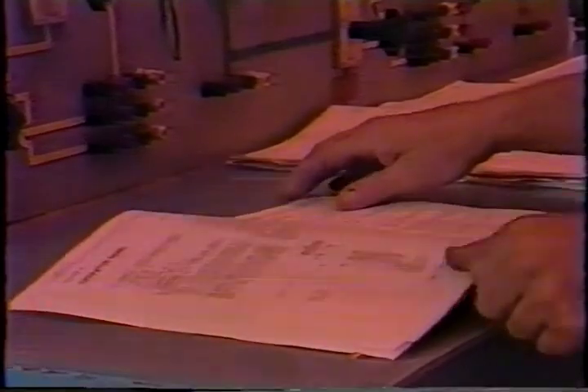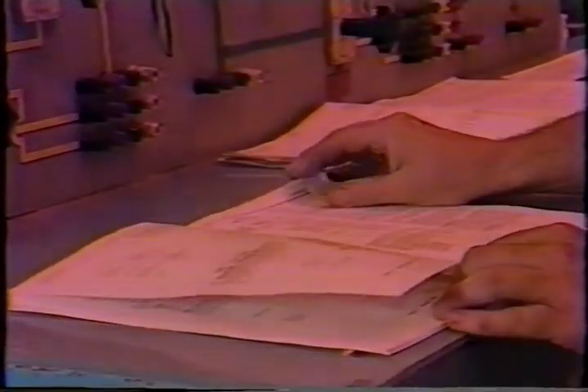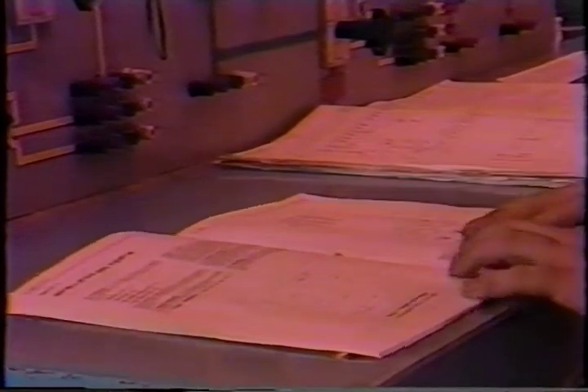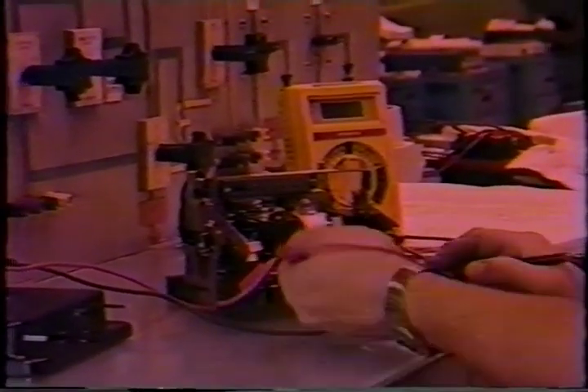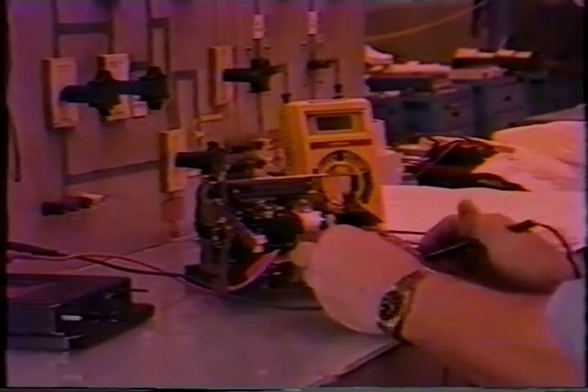The maintenance schedule for individual devices such as circuit breakers, relays, etc. should be based upon recommendations contained in the individual instruction book for the device. The switchgear installation should be given a thorough overall maintenance check at the end of the first year in service because it provides an opportunity to evaluate conditions at an early point in the life of the equipment. Where conditions are abnormal, more frequent inspection and maintenance is necessary. Where conditions warrant, a longer period of time between maintenance periods may be used. The following require attention.